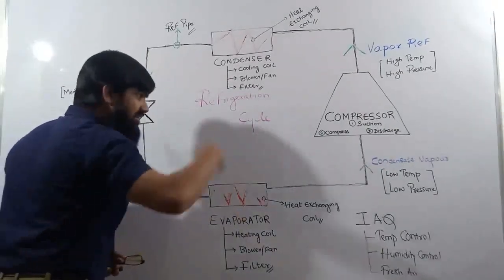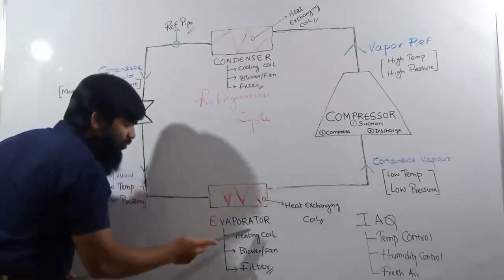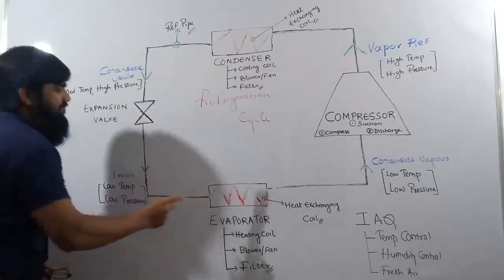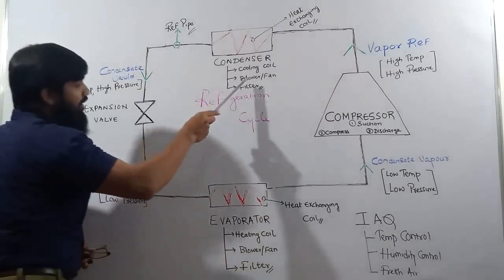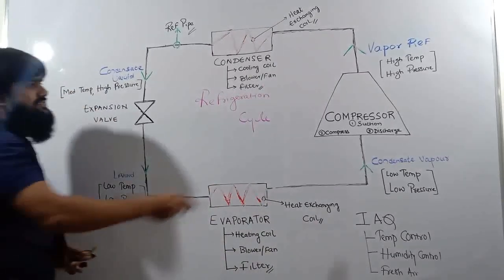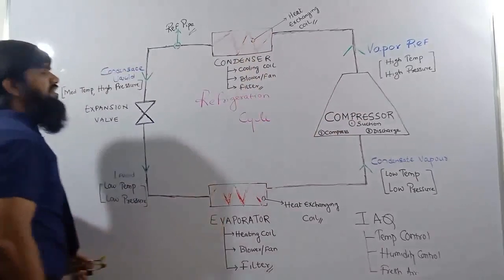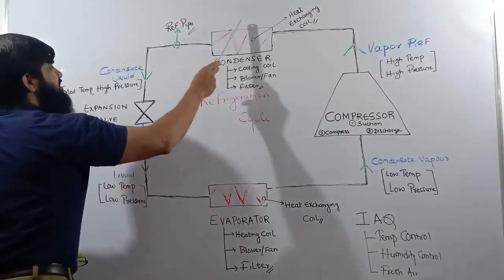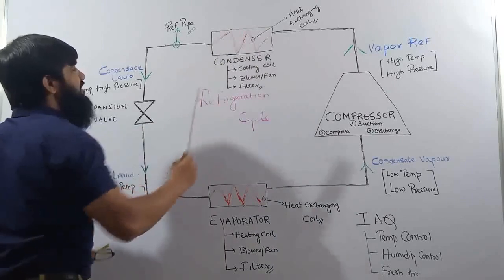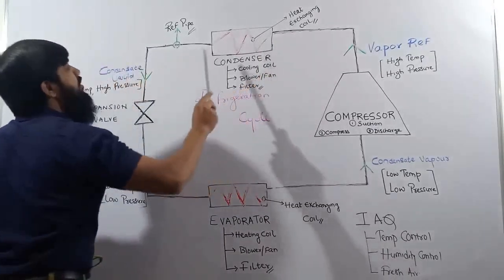Within this cycle, you will find heat exchanging coils in two components: one in the condenser and one in the evaporator. You will also find a blower, fan, and filter. From the output of the compressor, we get high temperature, high pressure vapor refrigerant entering the condenser. The condenser has a blower and a set of cooling coils. The condenser rejects the heat of the refrigerant coming from the compressor to the atmosphere.